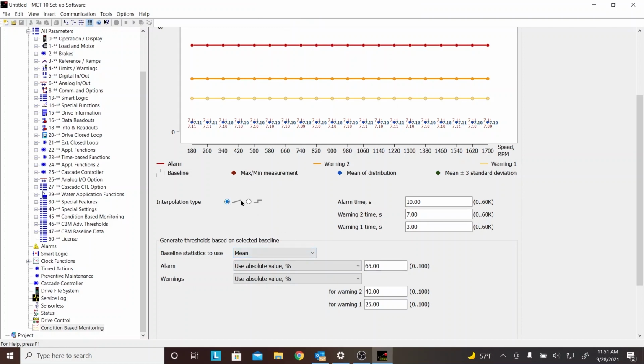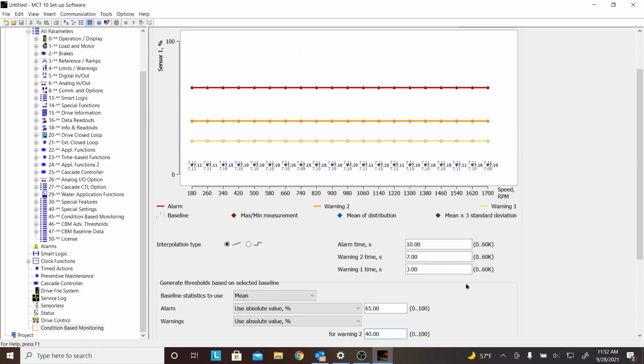But we can set the interpolation either linear or step, easy enough. We have choices for average, which is mean, or standard deviations if you're not a statistician. We have choices for how to set the alarms and the warnings with absolute or offsets, etc. And then we would plug in these numbers, easy enough to set. We would plug in a number. Let me just change this so you can see where it's coming up, and we can easily set that in there. We also have warnings in here, the time delays. So these are warning time delays and alarm time delays. If we set these up when we fall into a warning or we fall into an actual alarm, this will give us a delay before we get a communication of that warning or alarm. So that helps with nuisance trips or any of that, bad information we might get depending on how the process is running.